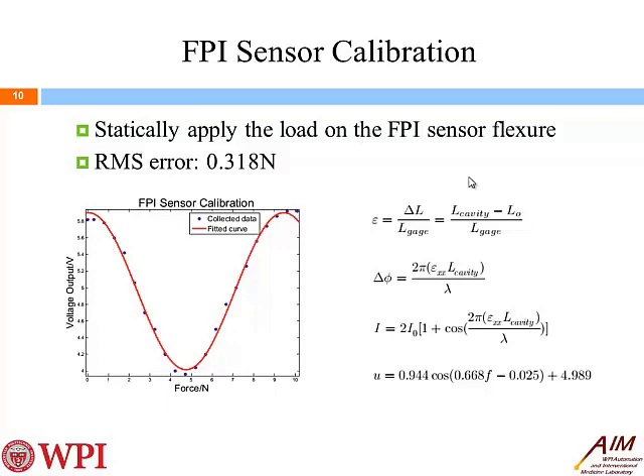So the calibration of this FPI sensor is conducted by adding a standard weight on the flexure. The weight is added to the stage of the FPI sensor flexure in the same direction, position, and area as the real motor drive rods contact with the flexure, so that the measured force is in the same direction as the real needle insertion force.